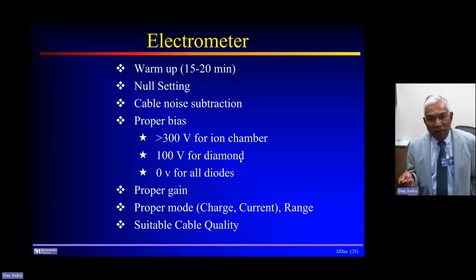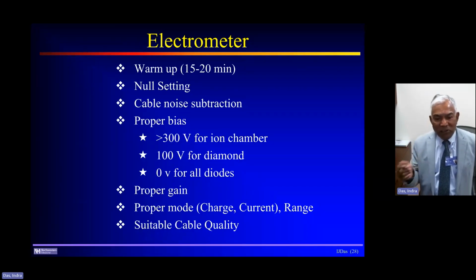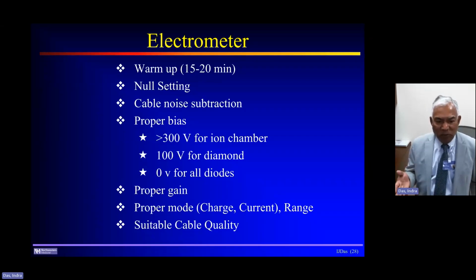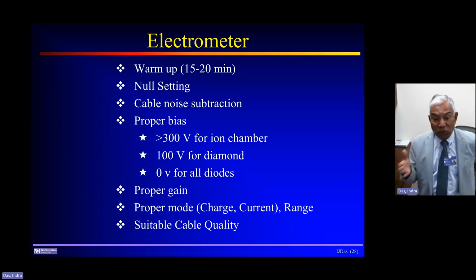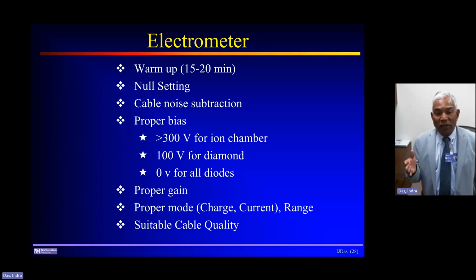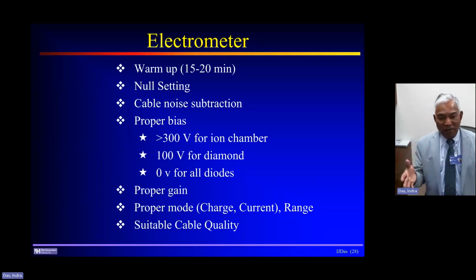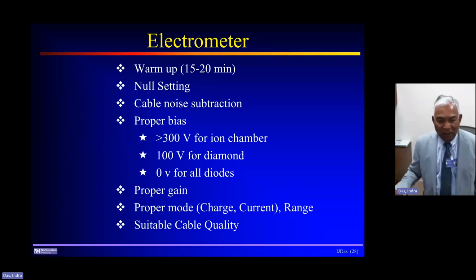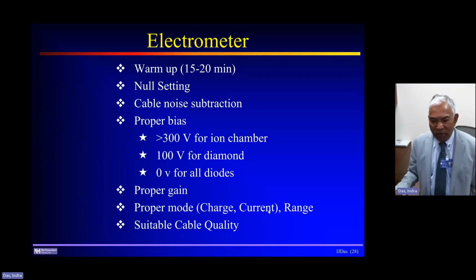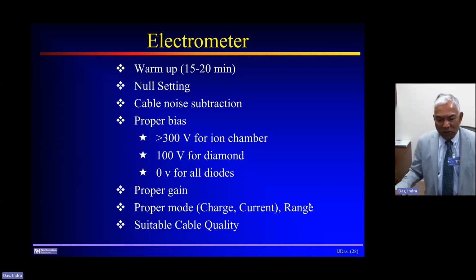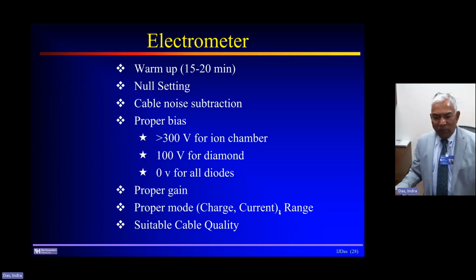Sometimes the electrometers reset themselves when you turn them off. They reset the voltage, but some of them just keep the voltage. So make sure that before you connect, the voltage is either set to 0 or to the proper value. Use the proper gain, proper mode, obviously charge mode or current, and then the range, because whether it is nanocoulombs or picocoulombs becomes a problem.